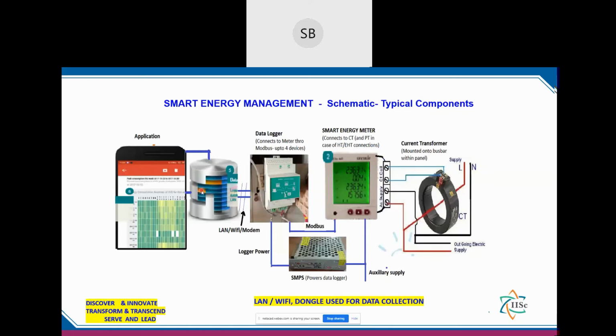The server is fed regularly, and as most of you know, if the substations are far off, sometimes the LAN connectivity may not be there. The entire information flow is through the LAN, the local area network, or Wi-Fi. In case neither is available and it's difficult to get the signals, we have a modem where the maintenance engineer carries the modem every week. Whatever information is stored gets transferred to the modem, and from the modem it is transferred to the server. This is how it is done in three ways.